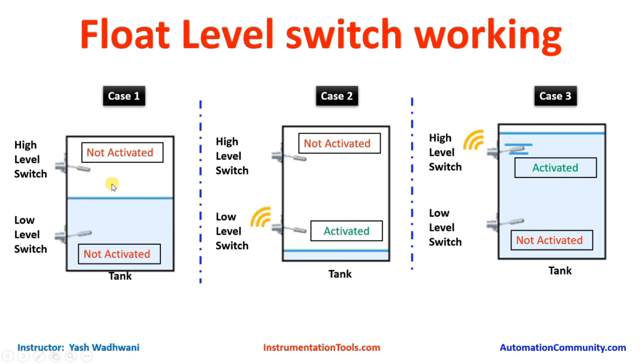As the pump starts, water begins filling. When the water rises above the low level switch, the low level switch will deactivate, but the pump will remain ON until the water level becomes higher than the high level float switch. At that point, the high level switch will be activated, give a signal to the PLC, and the PLC will stop the pump. In this way, the pump operates automatically based on the low level and high level switches.